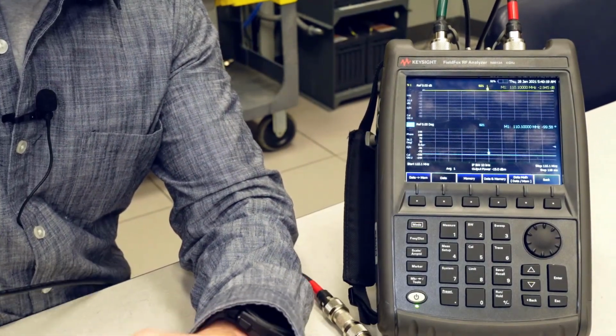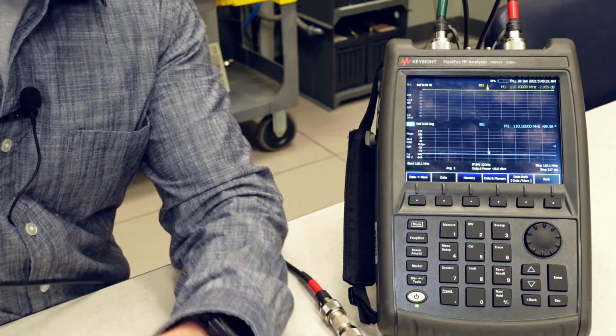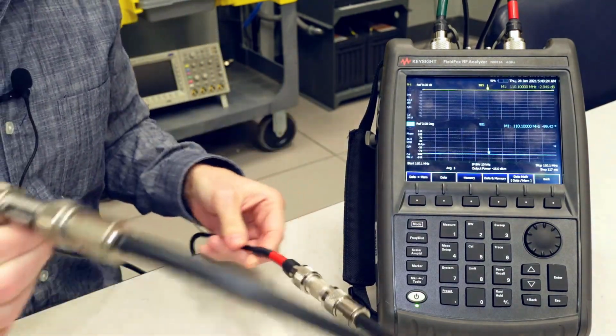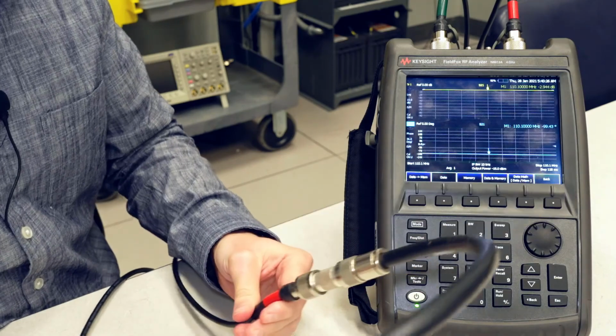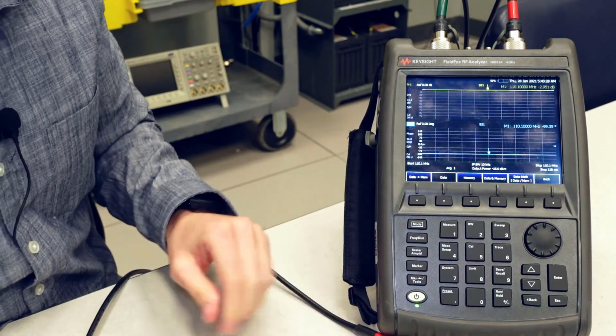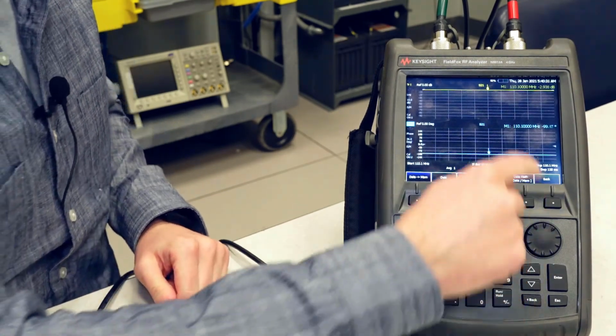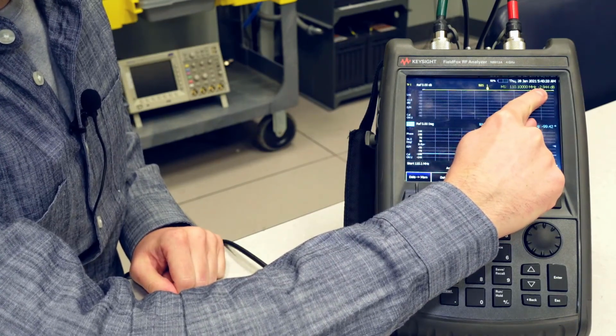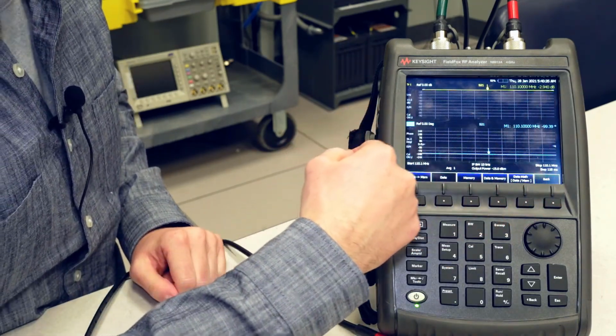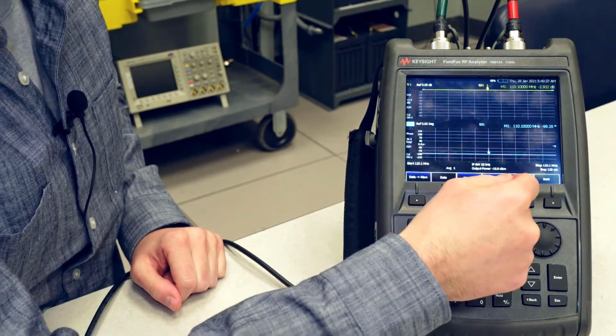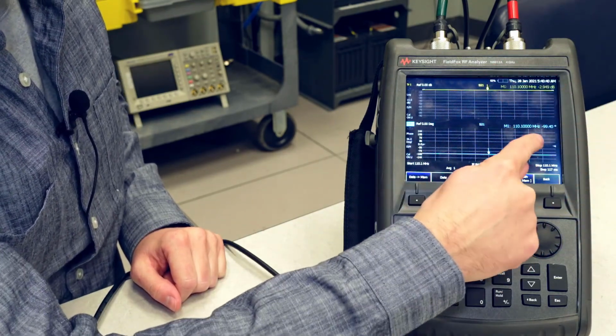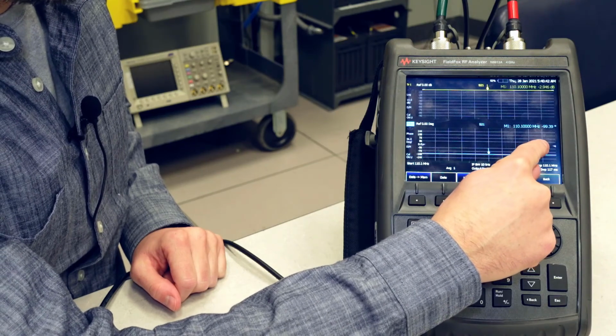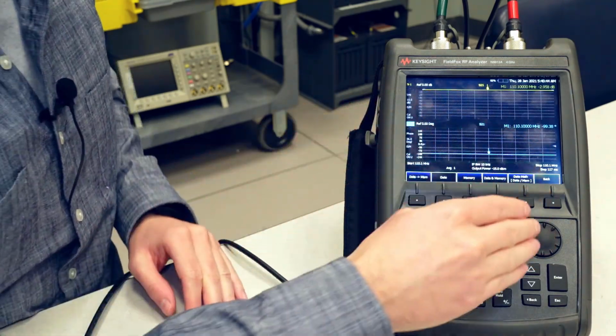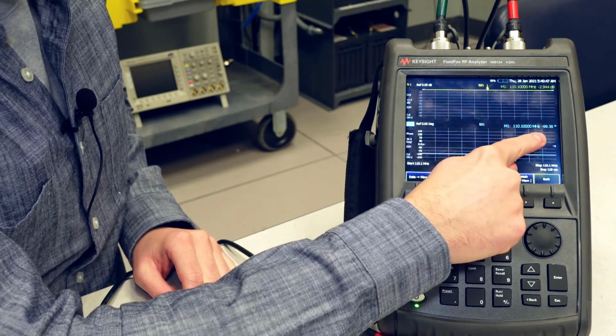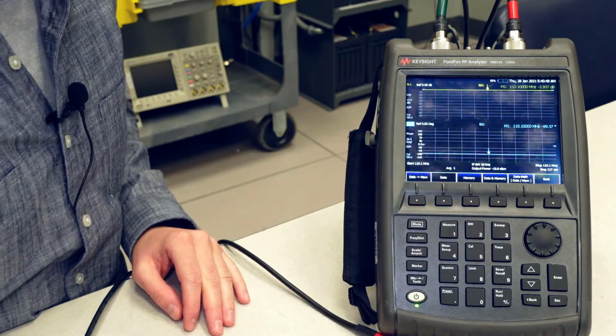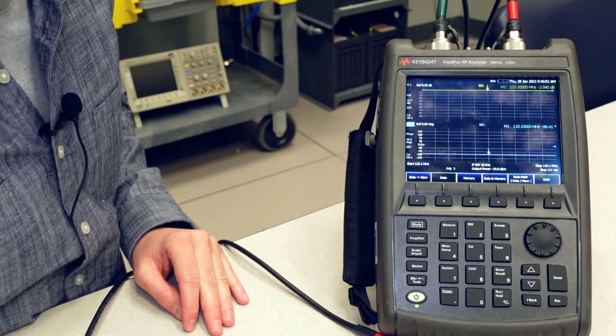There's nothing directional about this test cable, so it doesn't matter which port goes to which end on this setup. Now that we're connected, I'm reading a negative 2.93 dB. I usually only round to the nearest tenth, so negative 2.9 for amplitude, and for the phase, I'm reading a negative 99.3. I don't usually want to see a lot of fluctuation on these readings, definitely nothing more than a few tenths of a degree.